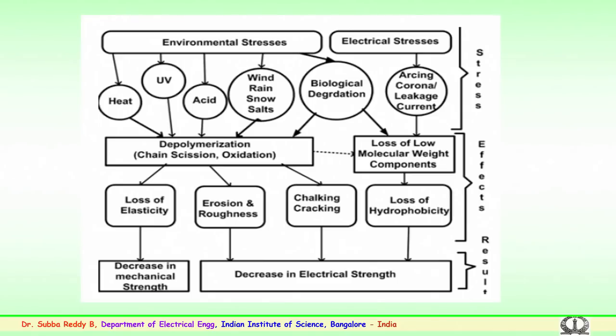As mentioned, if the water-repelling property of the polymer or composite insulator is lost, then the pollutants or the surface conditions due to wetting because of fog or snow would slowly try to make the entire surface, or the volume of the insulator surface, conducting. The degradation happens, the entire insulator starts conducting, and a flashover could also happen. These are some of the electrical effects which could happen over a period of time. This will definitely decrease the electrical strength.